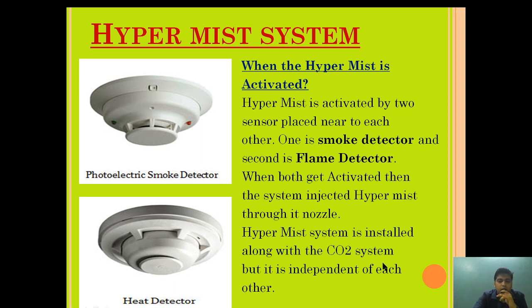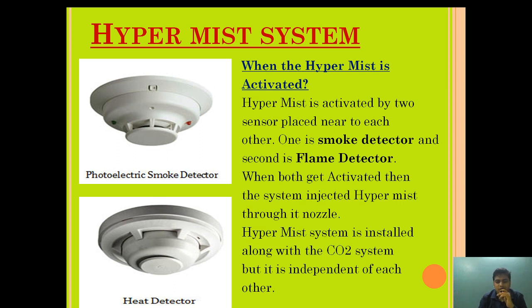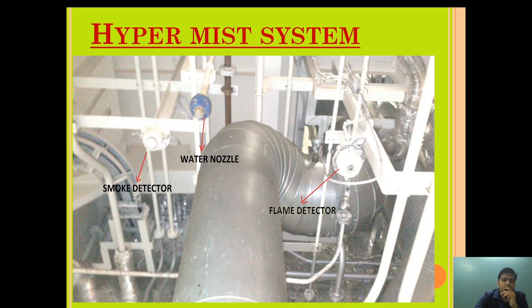When both detectors activate, the system injects Hypermist through its nozzle. The Hypermist is also provided along with the CO2 system, but both are independent of each other. For example, if a small fire takes place near an incinerator, we cannot inject CO2 into the whole engine room. Instead, the Hypermist — being an automatic system — will detect the fire and actuate once both smoke and flame detectors activate, extinguishing the fire locally. Both systems serve as independent fixed fire installations.